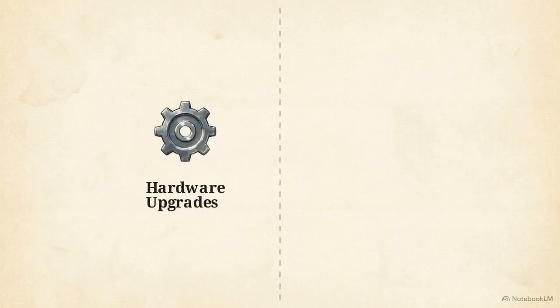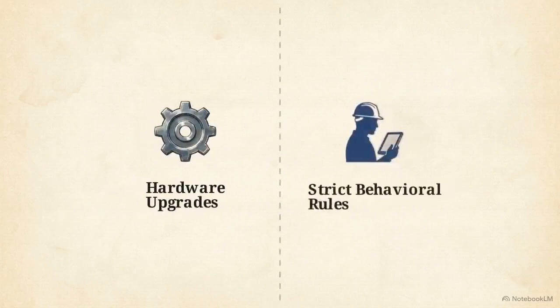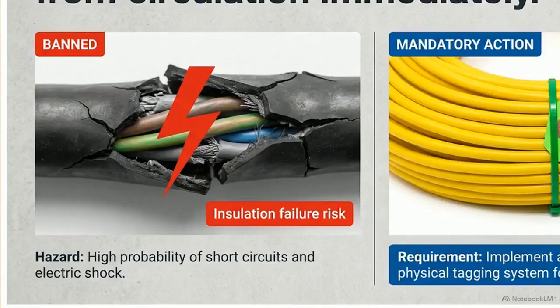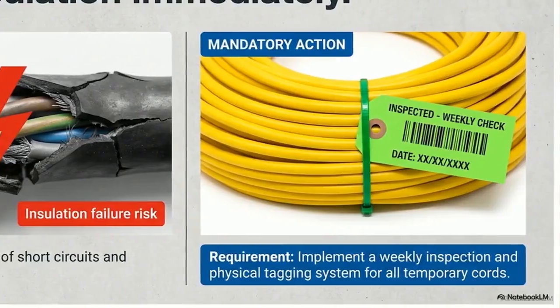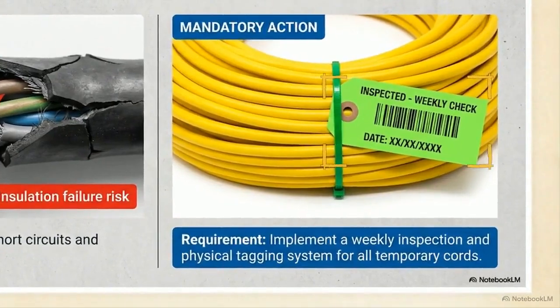Upgrading our hardware is only half the process. We also have to implement strict behavioral rules for how we manage temporary power. On the left, extension cords with split insulation or exposed wiring create a severe probability of short circuits. To fix this, we require the strict administrative control shown right. Every temporary cord must undergo weekly inspections and carry a physical tracking tag.